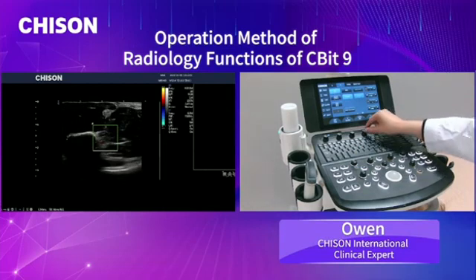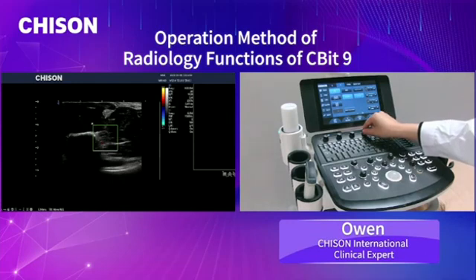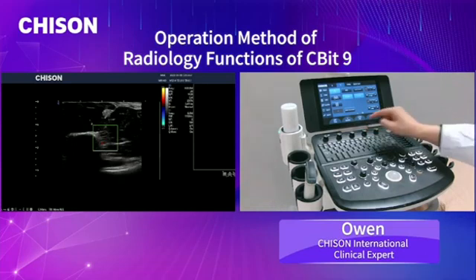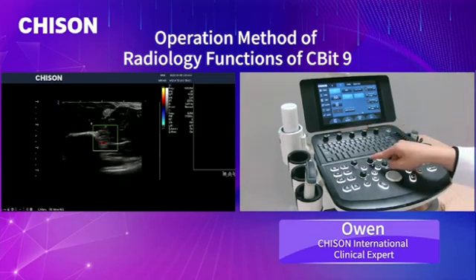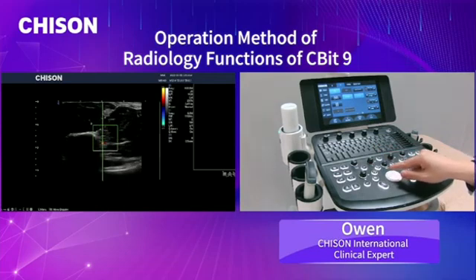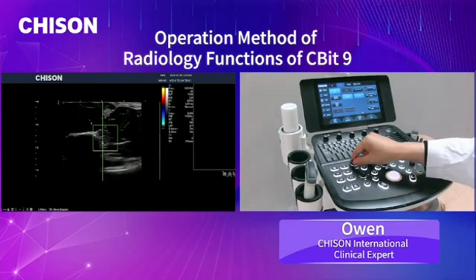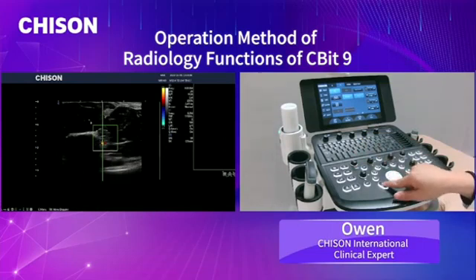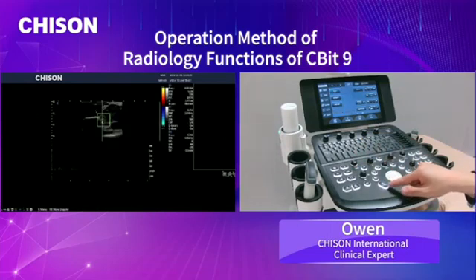Okay, here is the PRF value. You can decrease it a little bit to increase the color sensitivity. And this is for the Doppler mode. You press the D key and you can see the sample gate, and you can rotate the Doppler angle with the angle key, rotate it, and press the Update key to activate the spectrum.